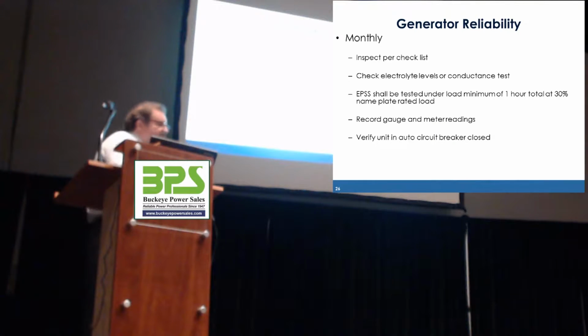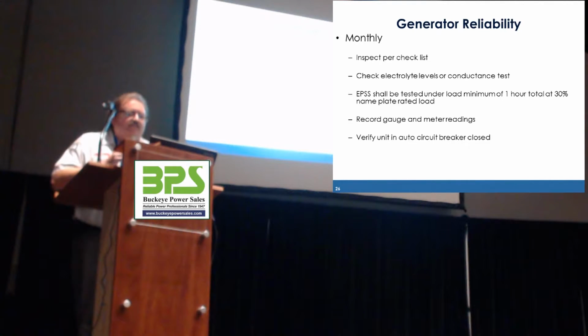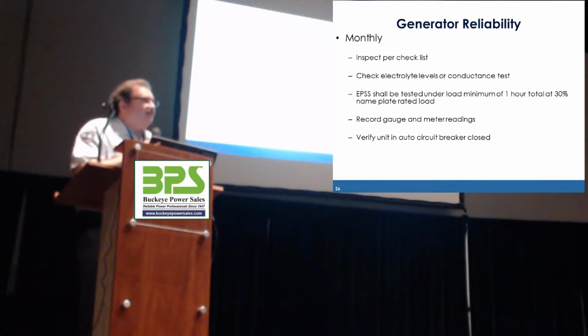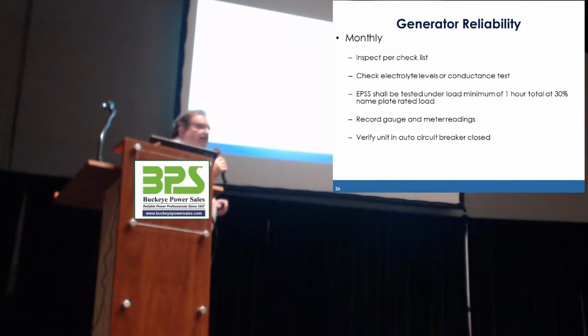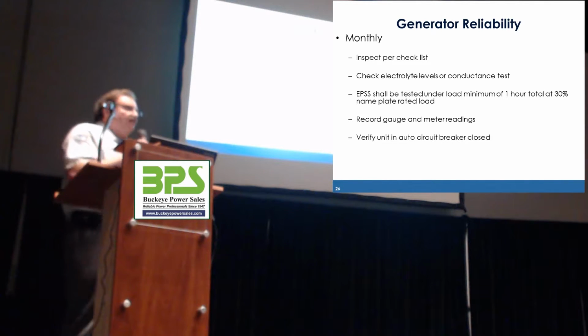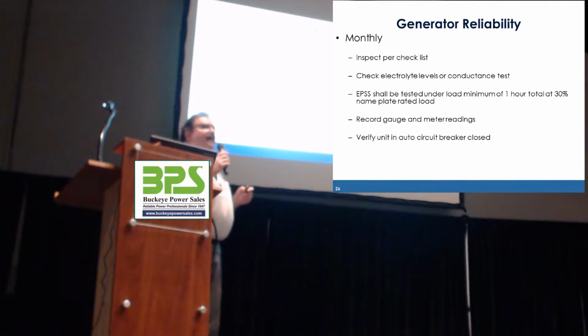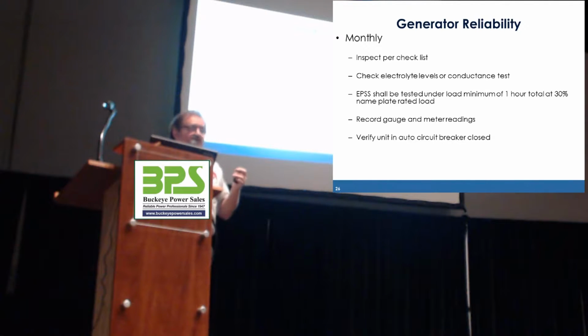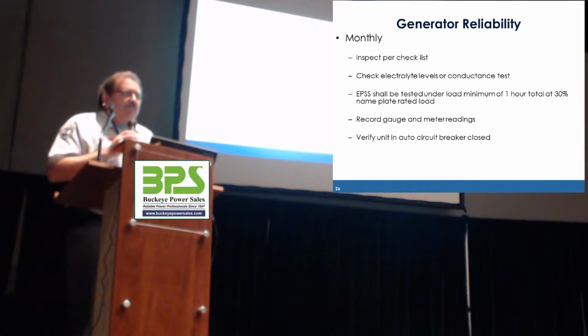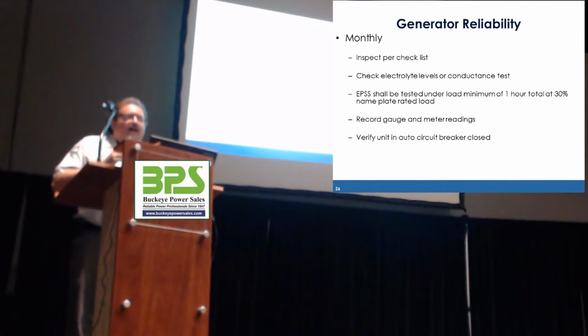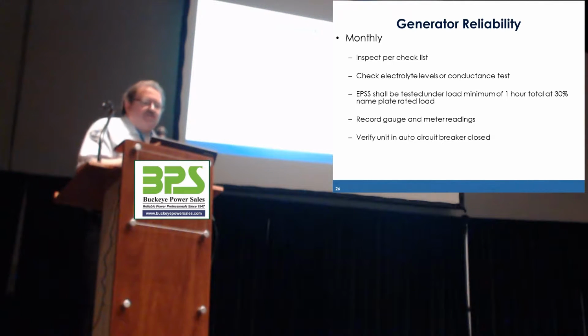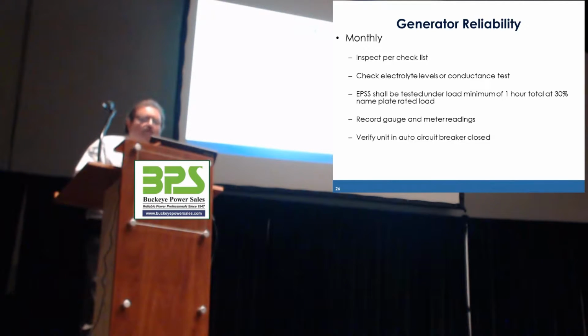The monthly checklist is very similar. We inspect it per that checklist. It also tells us that we have to check the electrolyte levels in the battery, or we can perform a conductance test. Now, checking the electrolyte in the batteries monthly requires a whole set of PPE because you're taking the caps off of a battery and looking at electrolyte. You have to have the proper training and the proper PPE to make sure that you're doing that in a safe manner. We'll touch base on that a little bit more.